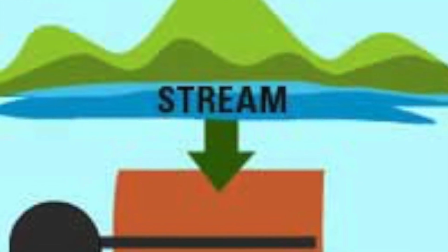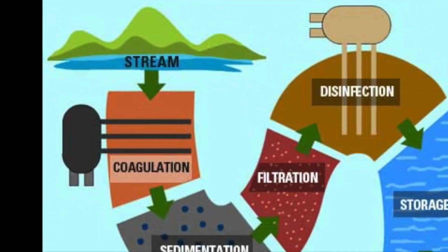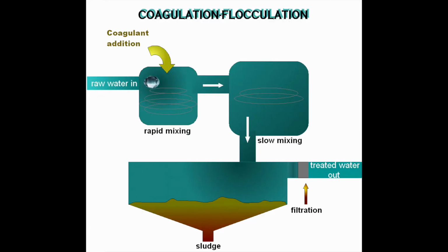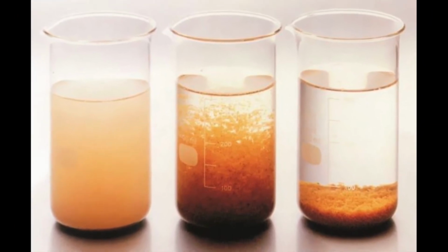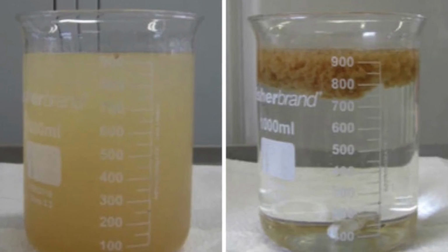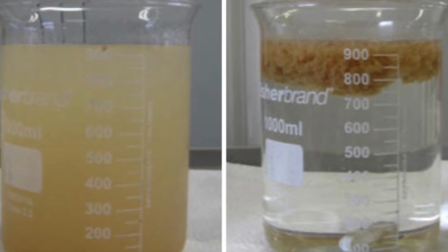Primary treatment. Water is added to a large holding tank where chemicals are added and the dirt or gross stuff coagulates, creating floc, or loosely combined masses of small particles. This water is left undisturbed to allow those heavy particles to sink to the bottom while grease and oil rise to the surface, making both of them easier to remove.